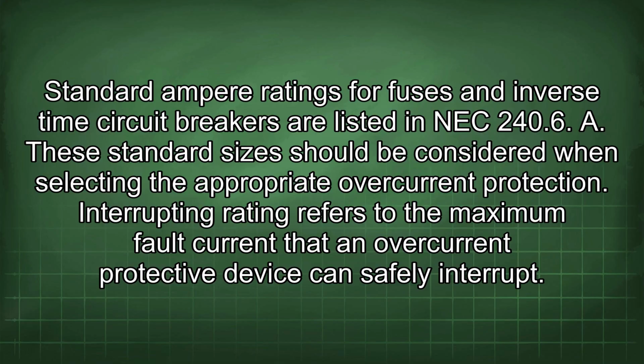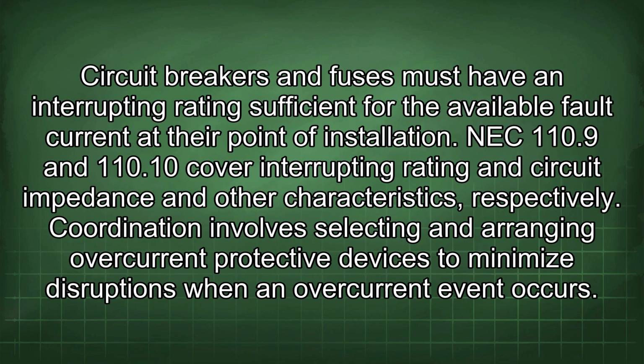These standard sizes should be considered when selecting the appropriate overcurrent protection. Interrupting rating refers to the maximum fault current that an overcurrent protective device can safely interrupt. Circuit breakers and fuses must have an interrupting rating sufficient for the available fault current at their point of installation. NEC 110.9 and 110.10 cover interrupting rating and circuit impedance and other characteristics, respectively.